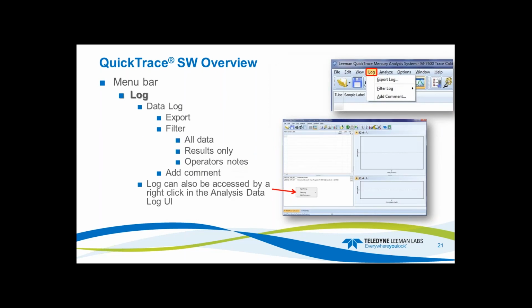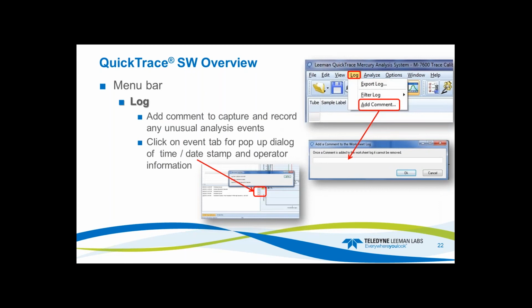Under Log, this is associated with the analysis UI, and down here in the bottom left-hand corner, it records and enters everything that happens during the analysis run. So you can review it later, you can print it out, and this is all for data quality control. You can export here, you can filter all data, results only, operator notes, add comments, and it can be accessed by right-clicking on the analysis data UI. So you just right-click and it pops up. You can add a comment, and that will capture and record any unusual analysis events during that run. So it's very nice for the technician and/or chemist to communicate back and forth with the quality control personnel on what's happening with the data. And then you can also click on the event tab, and that will pop up a dialog right here with time, date stamp, and operator information associated with that event.